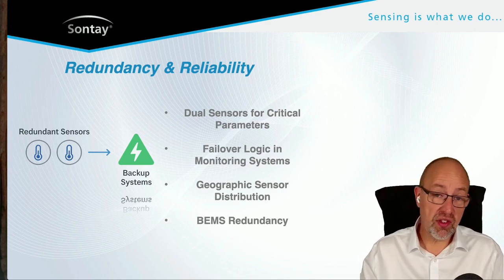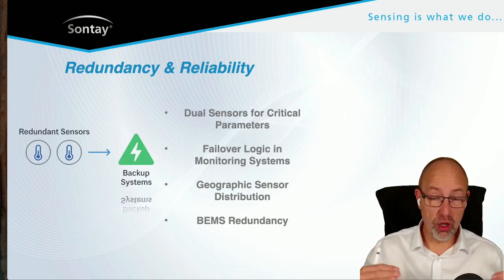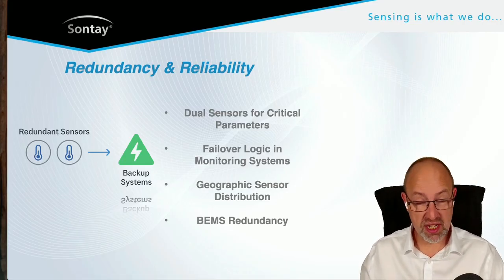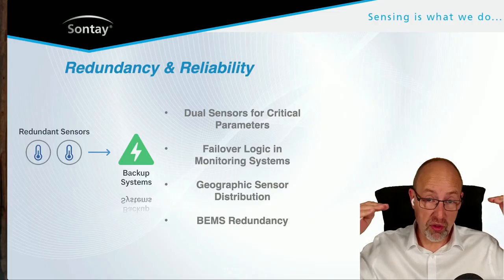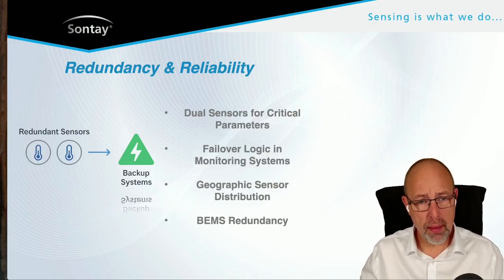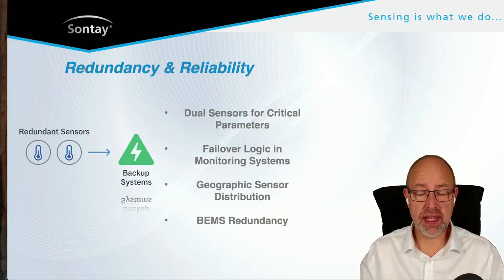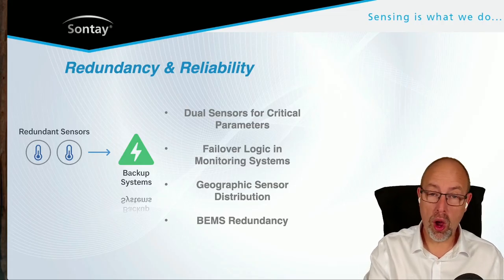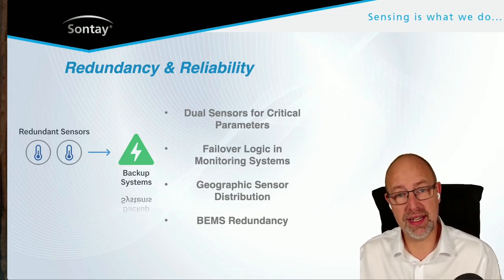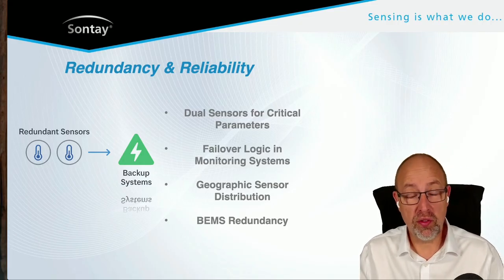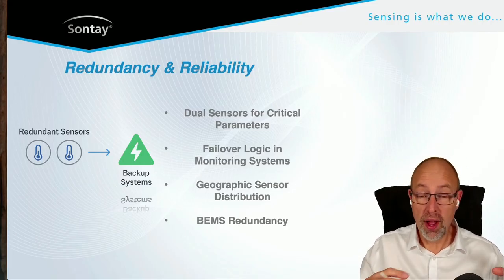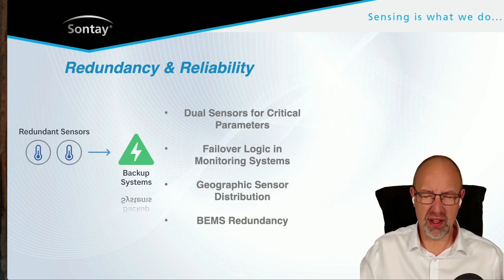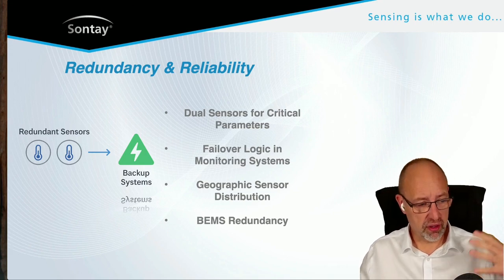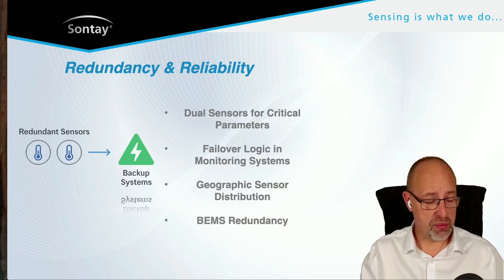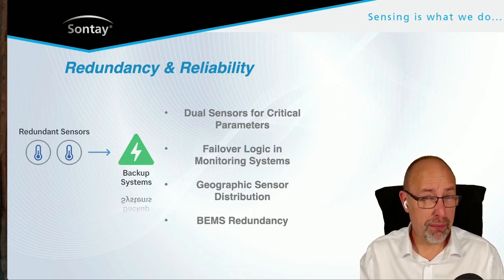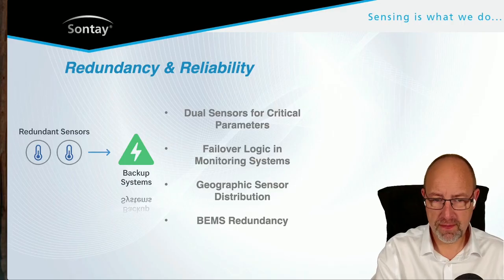Geographic sensor distribution is very important, as we've seen with hot aisle, cold aisle, looking at temperature differences above and below the racks. Beyond the sensors, we also need to think about BEMS redundancy. If you've got one controller connected to UPS A and one connected to UPS B, that gives us as much redundancy as we can get. Bear in mind data halls are huge—if you're getting a failure of your A and B power supplies, the BEMS is going to be the least of your worries at that point.